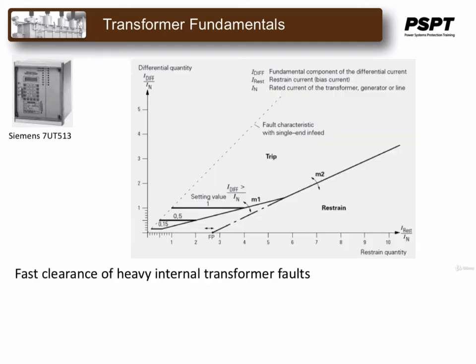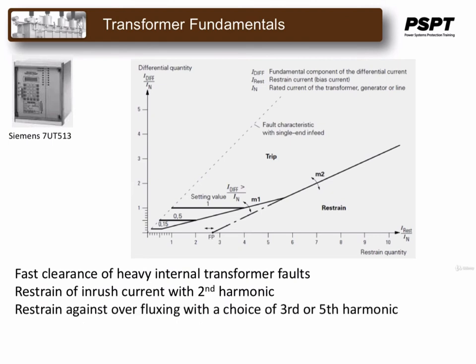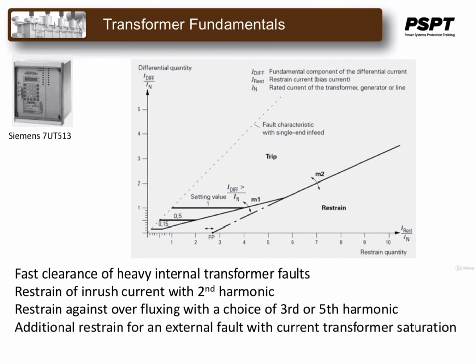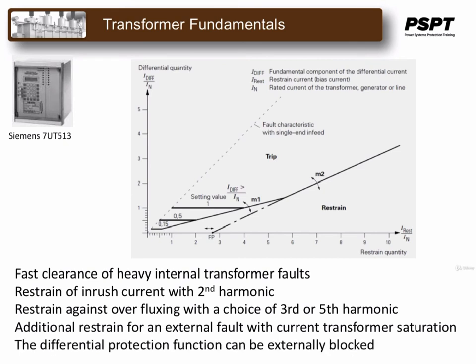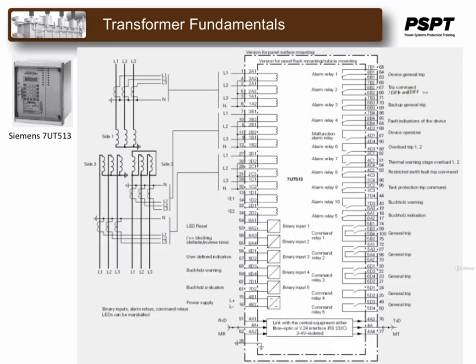This relay has fast clearance for heavy internal transformer faults. It also has a restraint of inrush current, recognizing second harmonics. It has restraint against overfluxing with a choice of third or fifth harmonic recognition. Additional restraint for external faults with current transformer saturation. And the differential protection function can be externally blocked if required. And just out of interest, this is how the Siemens 7UT513 is connected to the system.